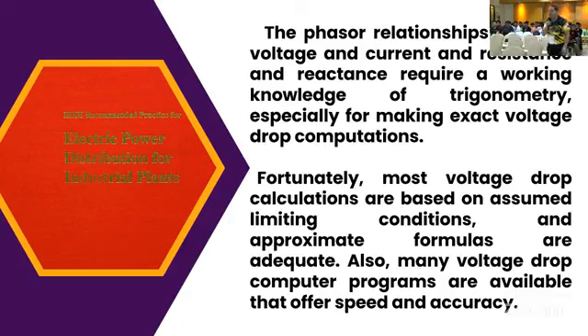Then, fortunately, most voltage drop calculations are based on assumed limiting conditions, and approximate formulas are adequate. Also, many voltage drop computer programs are available that offer speed and accuracy. Halimbawa, yung project ko dito sa isang project somewhere in Mindanao, hindi na-approve yung permit kasi kulang ng voltage drop. Now, yung substation po natin is 5 MVA. So pag 5 MVA, compute natin yung voltage drop from the substation to the load. Tama po ba? So pag kinumpute natin yan manually, mahihirapan po tayo. So ginamit ko, I use SKM PowerTools to compute the voltage drop. So automatic, as long as you know the length of the conductor, the resistance and reactance of the conductor, wala, dire-diretso na yan. Click, compute. Mayroon ng voltage drop.